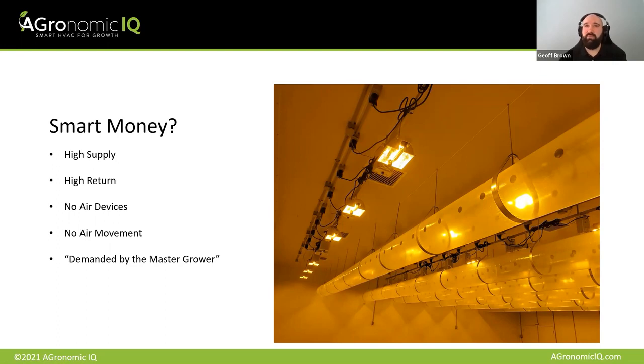So in general terms, I'm not a fan of air rotation fans in a space. They basically are energy pigs. They're not particularly efficient at moving air around, and they tend to be applied more universally than they ought to be. You can achieve good air movement in the space just with good ductwork design and not have that energy penalty of that extra set of fans. Again, any plug load in that space, any energy you spend in that space, you also have to spend energy cooling that energy, right?